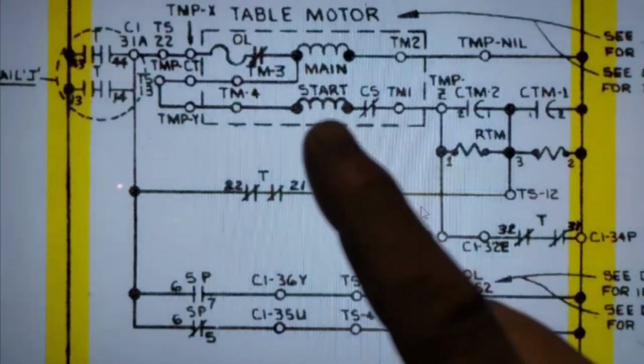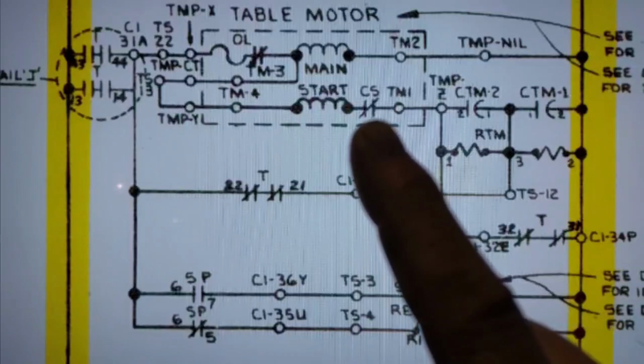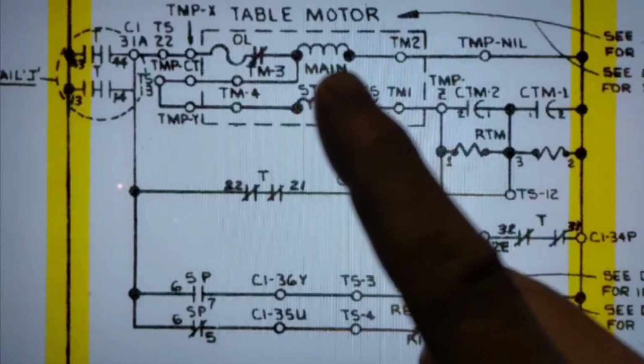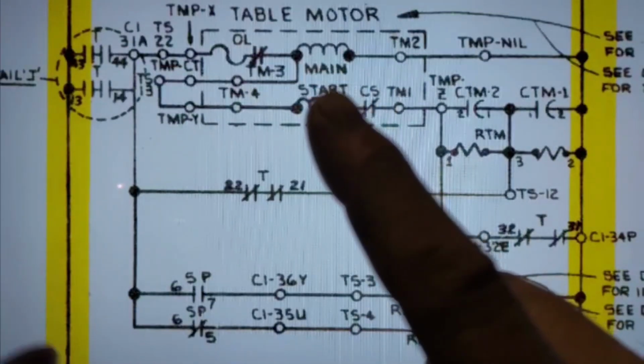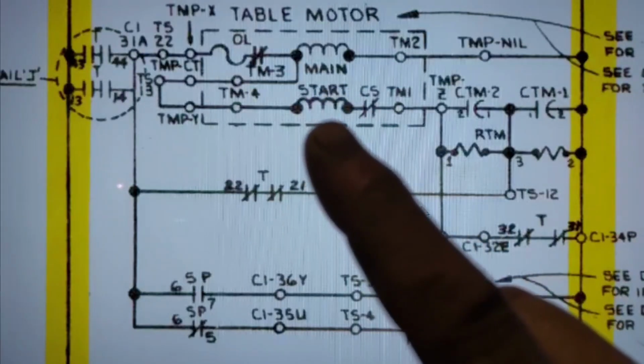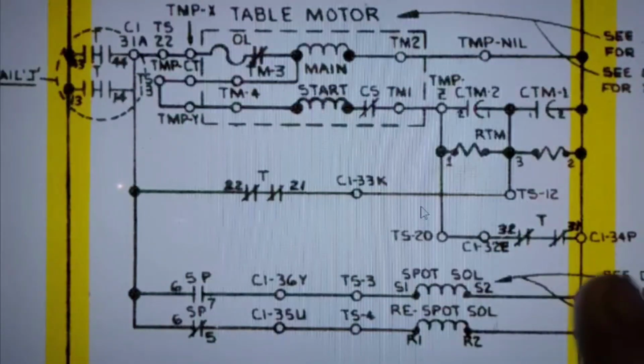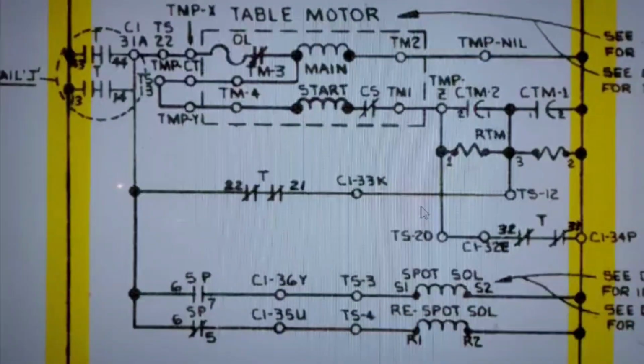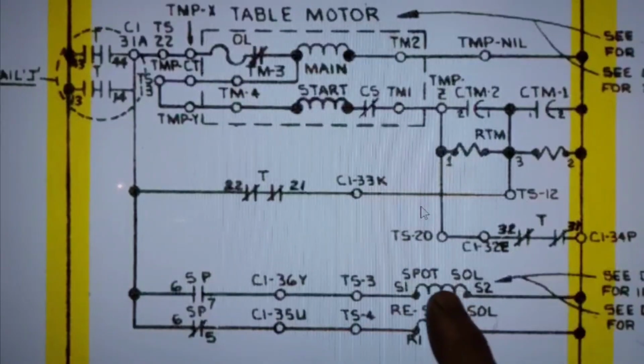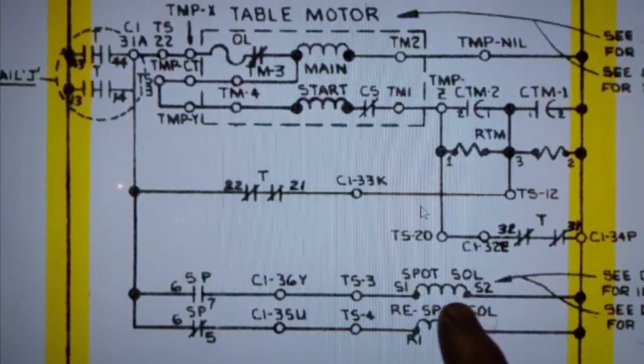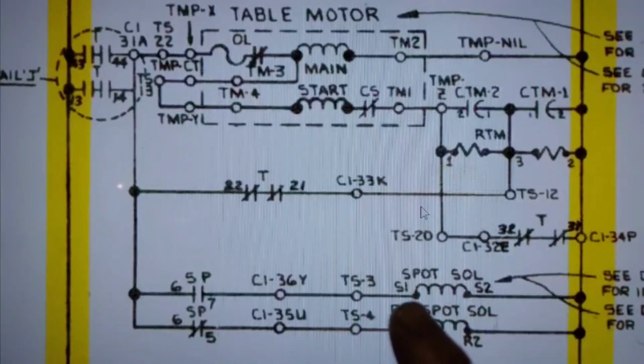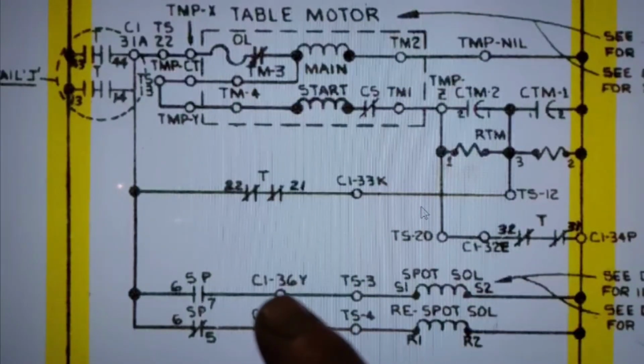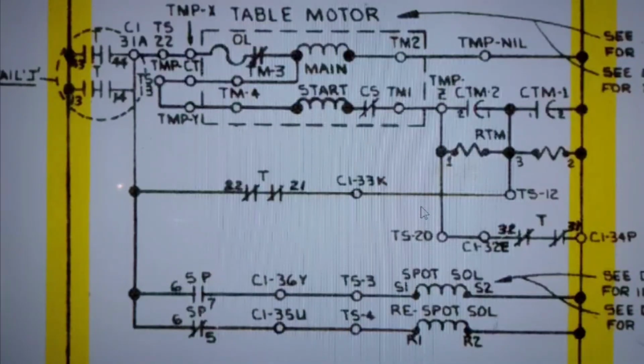But that way, the lamp will light up. There is no centrifugal switch, so the lamp, of course, will stay lit the whole time that the synchronous motor is running. But at least we know that the chassis was supplying a neutral to the start windings to get the table motor running. For the spot relay, to see when it's in spot cycle, make sure it's pulling in the spot relay. One leg of your lamp goes straight to the neutral. The hot side is going to come in through 36Y. And that would indicate that the machine is in spot cycle.